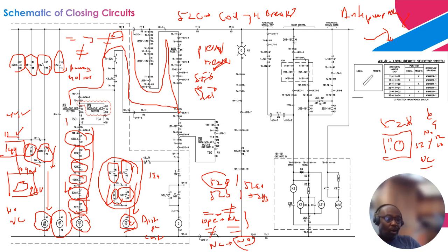Okay, so on this side is basically the indication from the protective relay, the transmission line protective relay, right? Indication has to come from that relay to tell you that relay is ready. That's a self-check status from this relay. So either this or this, they are in parallel, right? That indication from this one, or that indication from this other relay, the two relays, primary and secondary transmission line relays. The contact has to change state from normally open to normally closed to give that indication, to allow the closing permissive string to perform its function.